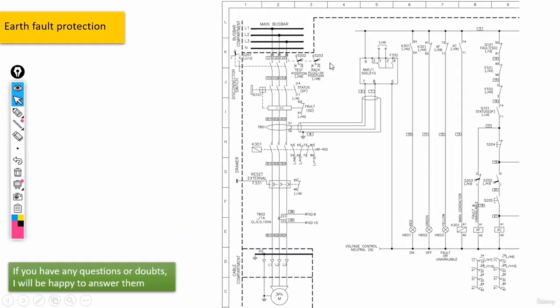Now, let me give you an example. I'm going to show you a real diagram regarding this whole concept. Okay, we have this diagram for a real control circuit. Up here, we have the three phases entering our electrical panel. Then here we got this manual switch. After that, we have this MCCB breaker. And then the transformer, the CBCT transformer. And well, obviously the transformer is connected to the earth fault relay here. And there's this contactor here that we would use for turning on the three-phase motor.